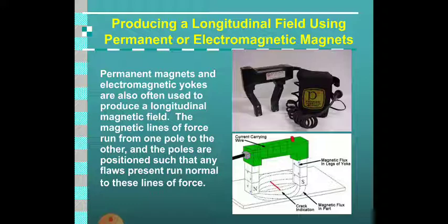For this reason, a low open circuit voltage of 2 to 16 volts is utilized, and this method provides only a unidirectional magnetic field. Therefore, it is necessary to reorient the contacts by about 90 degrees and remagnetize to inspect the complete area.